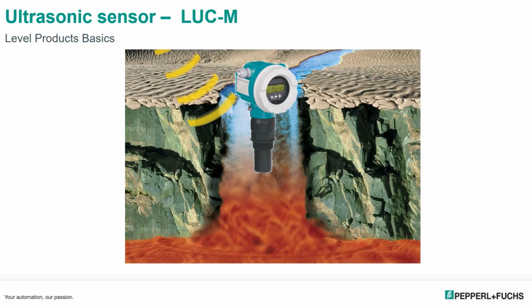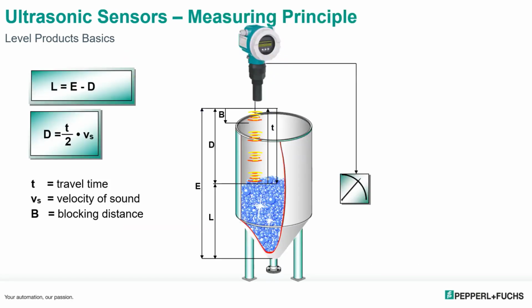The LUC-M is an ultrasonic sensor. It will actually send out a sound wave from the probe, which bounces off the medium and comes back to the probe head, and the amount of time it takes to send and receive will indicate where the level is in the tank. As you can see here, it sends out a signal, bounces off the medium, and comes back. Now, with the ultrasonic, because of the speed of sound, there's a certain blocking distance from the probe head down that cannot be used. However, that's very short compared to the length of the medium it can detect.